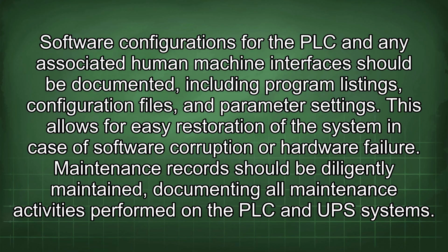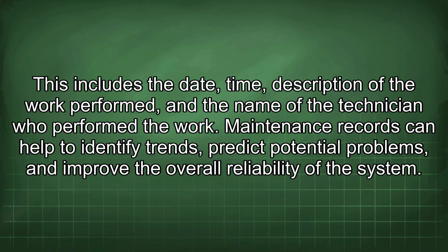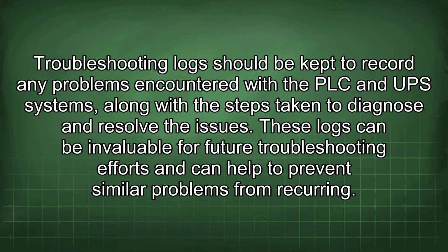Maintenance records should be diligently maintained, documenting all maintenance activities performed on the PLC and UPS systems. This includes the date, time, description of the work performed, and the name of the technician who performed the work. Maintenance records can help to identify trends, predict potential problems, and improve the overall reliability of the system. Troubleshooting logs should be kept to record any problems encountered with the PLC and UPS systems, along with the steps taken to diagnose and resolve the issues. These logs can be invaluable for future troubleshooting efforts and can help to prevent similar problems from occurring.